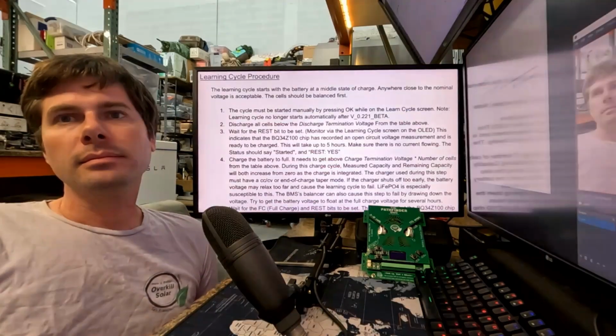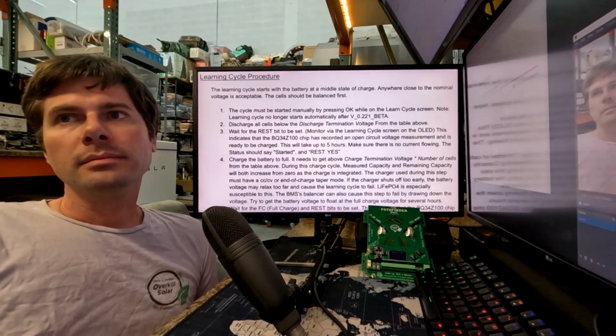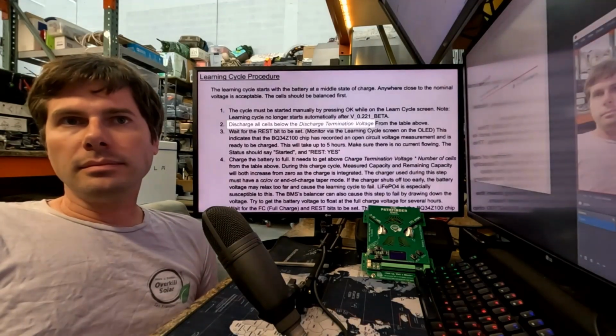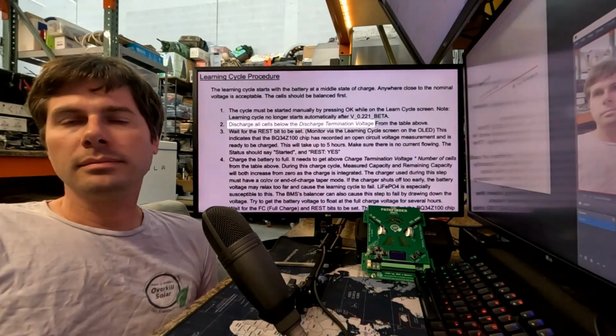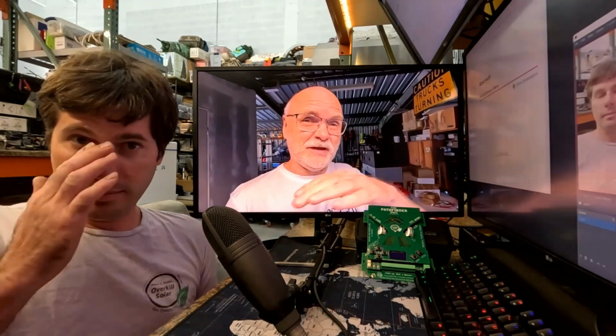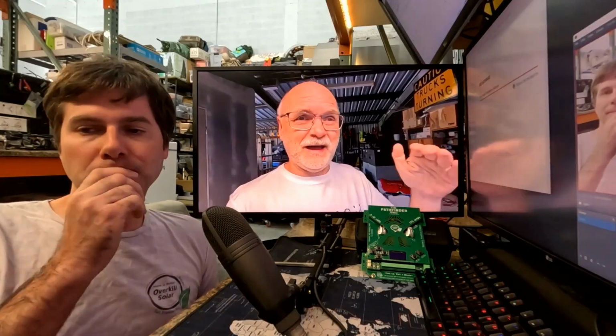To do this capacity learning cycle, it is fairly easy to follow these 7 steps in the manual. We basically start with discharging the battery now to under 48 volts and then wait for the rest bit to set. The BMS, this special big huge chip, looks for a stable voltage under 48 volts for quite a while, and then it says, okay, we are down to 48 volts, we are not charging or discharging any further.